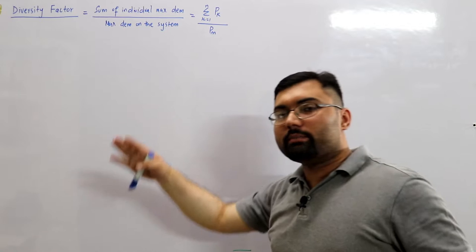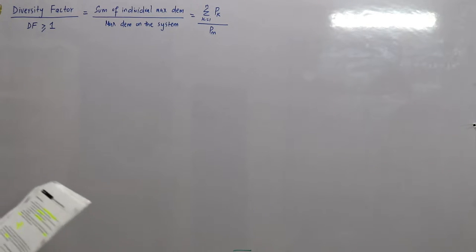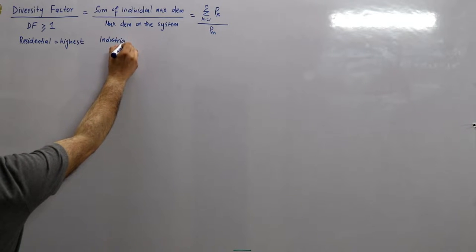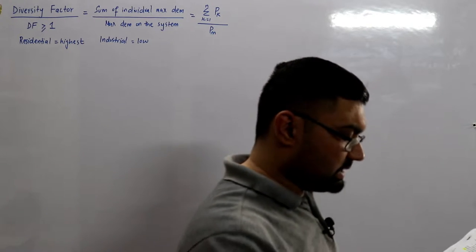Of course, the sum of all the individual maximum demands would be greater than the maximum demand of the system, which means the diversity factor DF is always greater than or equal to 1. Residential loads have the highest diversity factors, whereas industrial loads have lower diversity factors. Street lights have a diversity factor practically equal to unity, and other loads vary between these limits.